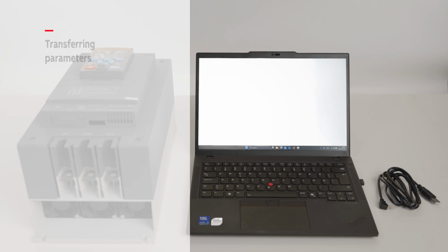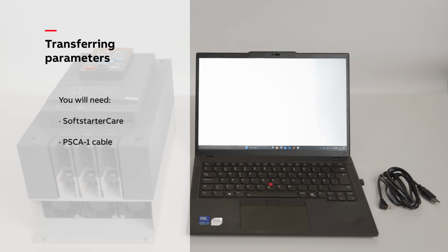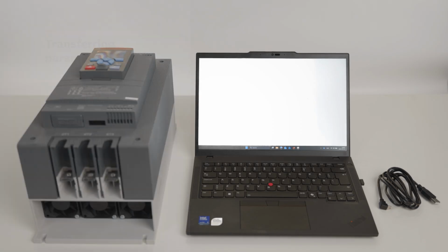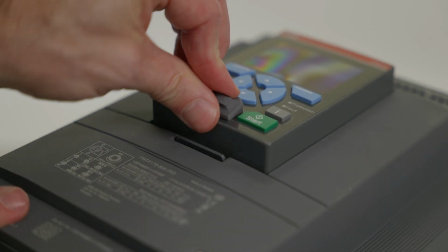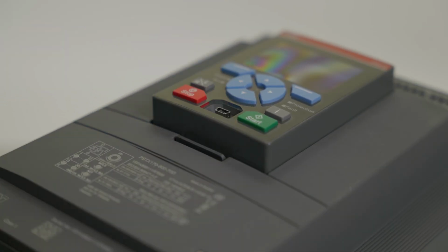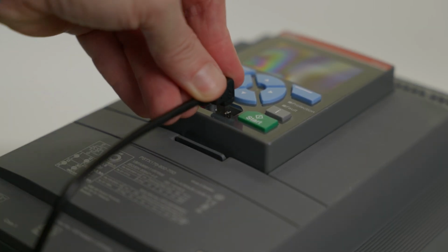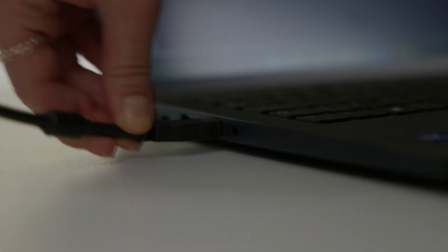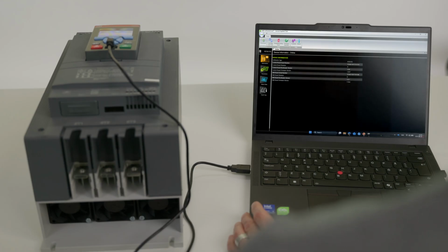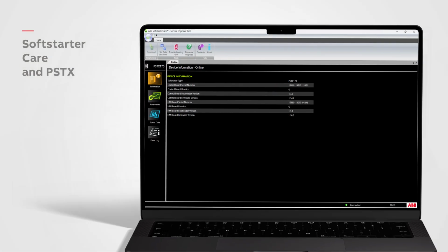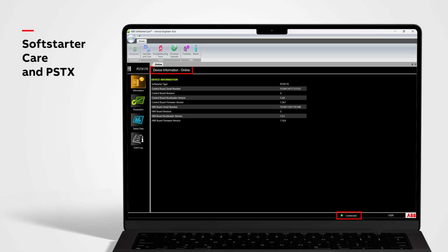In this final section, we will transfer the parameters to a physical device. You will need a mini USB to USB data cable available as an accessory in the ABB SoftstarterCare portfolio. Connect the mini USB plug to the PSTX HMI and the USB plug to your computer. Then open Softstarter Care. If the connection is successful, you will see a connected or online indication in the interface.